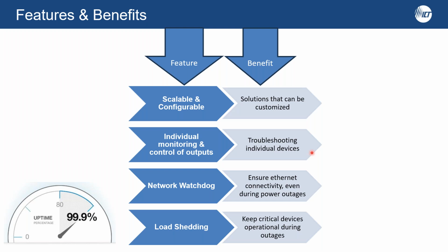Load shedding is critical when you have a particular backup time with batteries there, and you've lost AC power that isn't coming back. You want to enhance battery backup, so you can pre-select loads you know aren't critical for network operation, and define a voltage at which load shedding should happen. For a 48-volt system, which generally operates around 55.2 or 55.4 volts, with lead acid batteries in particular, the voltage keeps decreasing with load during backup use. So you can set a voltage, say 47 or 48 volts, for load shedding of a particular device, like a halogen lamp or any other non-critical device. Our system will load shed those particular loads and give your network more backup time.